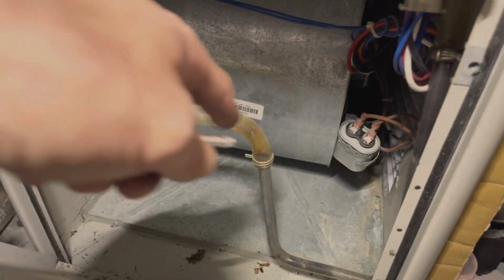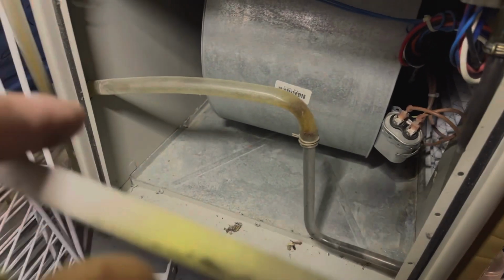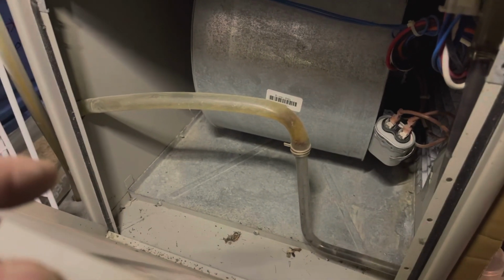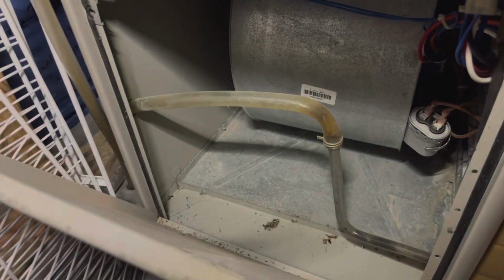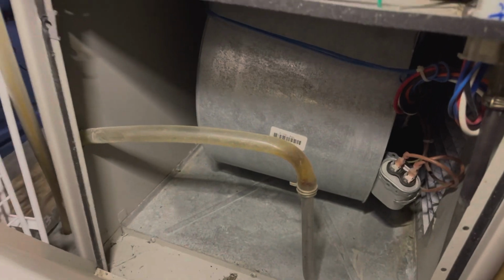So, since she wants to open this, we'll show you another common issue: you could have a dirty blower motor. The blades on the blower motor should be cleaned. Now, when this opens up, your furnace is going to turn off automatically because there's a little switch right here. So it knows that that's open. Here's one of your condensate lines. So you can get in here with a vacuum. You got to be careful. The blades on the blower motor can be sharp, but you can get in here with a small vacuum and clean these out. Maybe an air gun, blow out the blower blades, blower assembly there. It's a good idea to do that often.